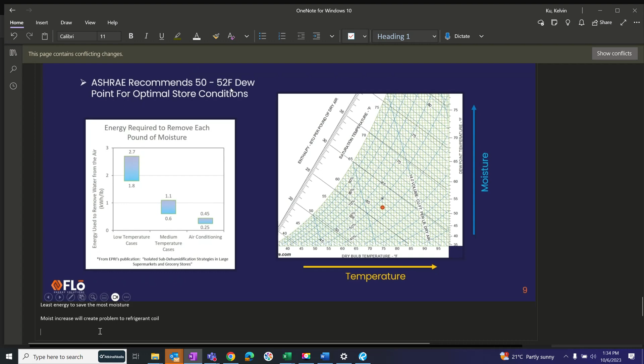And so they're designed to operate in an environment less than 55 dew point. And if you operate them above, you're outside of their warranty. Does that explain that? So it's really about freezing their coils, in which case they have to defrost. And you probably in refrigeration equipment know about the defrost cycles. The more frost we create on their coils, the more often they have to defrost. And so their defrost cycles go up, which means they're expending more energy to actually freeze them, thaw them, remove that moisture, and the cycle repeats.